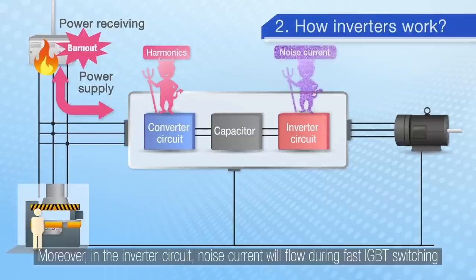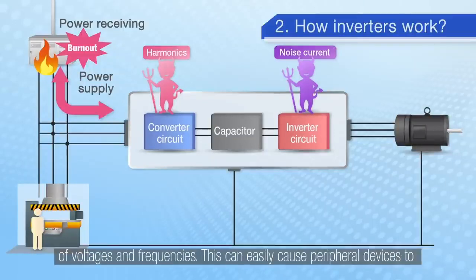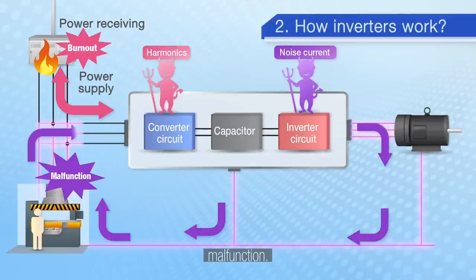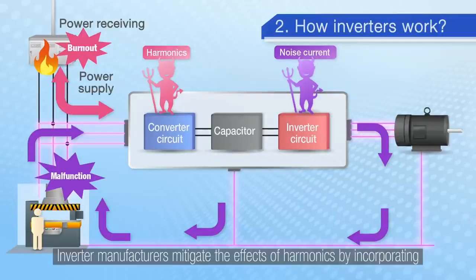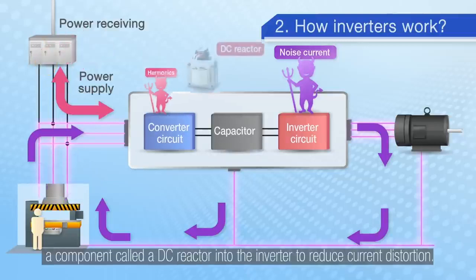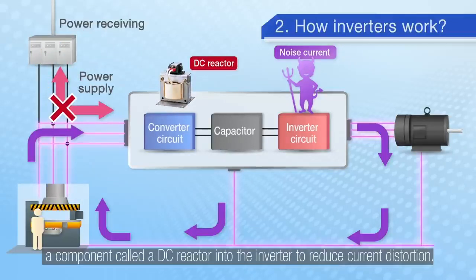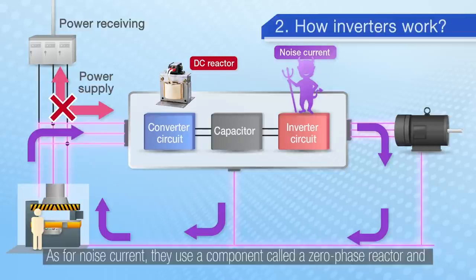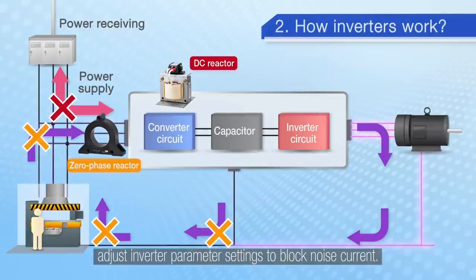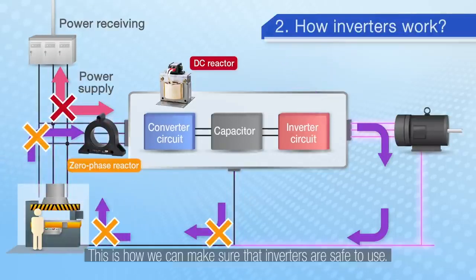Moreover, in the inverter circuit, noise current will flow during fast IGBT switching of voltages and frequencies. This can easily cause peripheral devices to malfunction. Inverter manufacturers mitigate the effects of harmonics by incorporating a component called a DC reactor into the inverter to reduce current distortion. As for noise current, they use a component called a zero-phase reactor and adjust inverter parameter settings to block noise current. This is how we make sure that the inverters are safe to use.